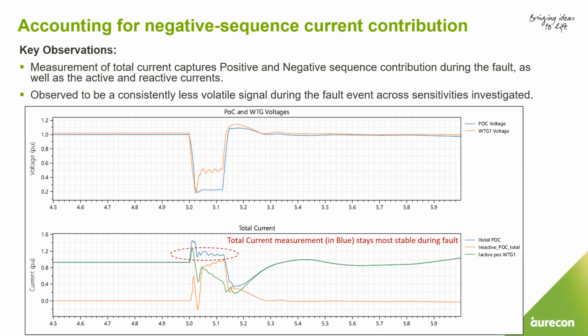With that in mind, consider another two-phase to ground fault, fairly similar if not identical, where voltage drops to around 20%. In this simulation graph we compare the positive sequence reactive current and the total reactive current, to see whether including both negative and positive sequence current would fix the problem, or whether we're missing something else. And last but not least, the total current, shown in blue.